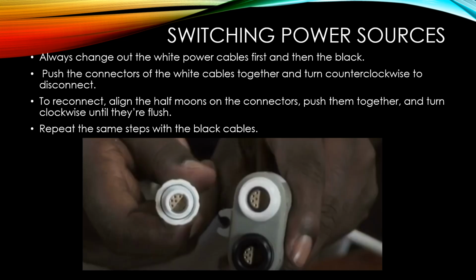Always change out the white power cables first, and then the black when switching power sources. This is the way that the patient is trained in the hospital. To switch out the cables, first push the connectors of the white cables together and turn counterclockwise to disconnect. To reconnect, align the half moons on the connectors, push them together, and turn clockwise until they're flush. Do not force them. Repeat the same steps with the black cables.